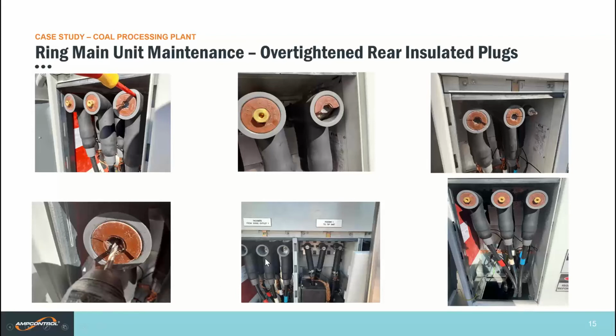broken RIP. Bottom photo there in the middle showing that we've got the RIPs out. Unfortunately, there's been some damage to the connecting pin, which is just shown in there. So they need to be replaced as well. The final photo there is basically the broken RIPs have been removed and new ones replaced on the screened elbows so they can go back into service.